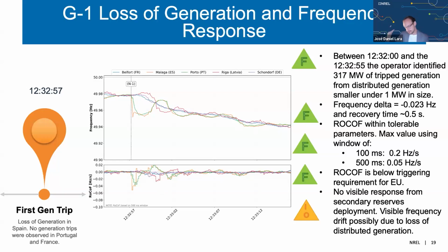And again, I want to point that out: as a community, we first figured that the rate of change of frequency was too high, but we realized here that it wasn't, right? But yet the frequency started to drop. So in this particular window of time, the maximum tolerance, depending on how you measure the rate of change of frequency, is 0.2 hertz or 0.05 hertz, which is pretty far away from the European regulation for actually tripping units due to rate of change of frequency.